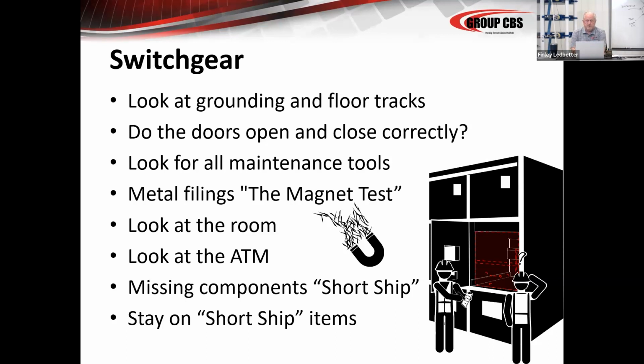So I typically carried a magnet for me. If I found filings, I'd take a magic marker and circle the spot in the cell floor. I'd pull the breaker out and look in that spot and see what device was there, and it would tell you what was cutting those filings. There should not be any metal filings in the floor of this metal clad switchgear after you do the standard acceptance testing.